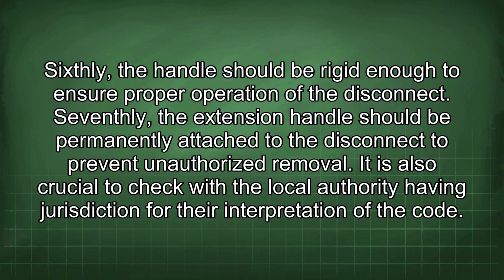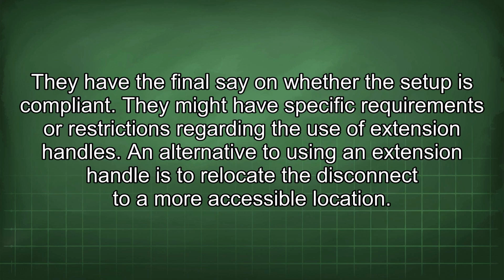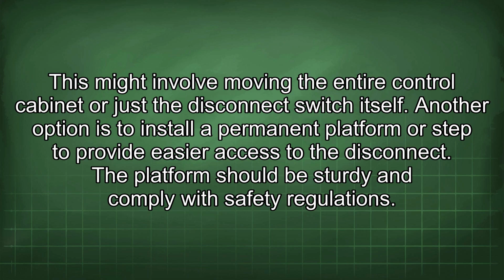It is also crucial to check with the local authority having jurisdiction for their interpretation of the code. They have the final say on whether the setup is compliant. They might have specific requirements or restrictions regarding the use of extension handles. An alternative to using an extension handle is to relocate the disconnect to a more accessible location. This might involve moving the entire control cabinet or just the disconnect switch itself. Another option is to install a permanent platform or step to provide easier access to the disconnect. The platform should be sturdy and comply with safety regulations.